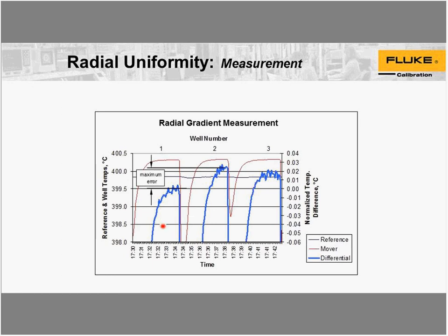So again, we're using the 2 thermometers. I'm going to measure the first one, let it come to a stable temperature. You can see this one could have been longer, but it's a noticeably stable level in that amount of time.